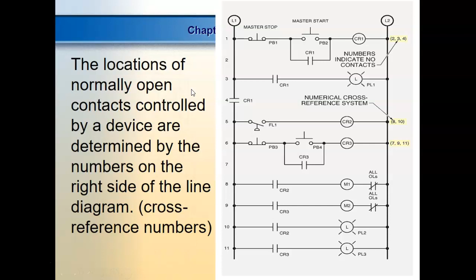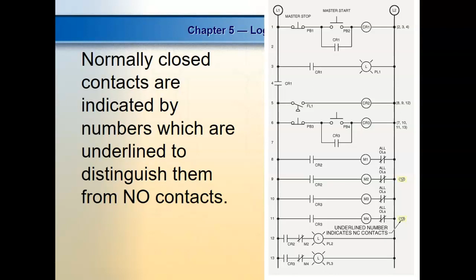All right, so normally closed contacts are indicated by numbers that are underlined. Whenever we use contacts that are normally closed, we underline them on the right. So our reference number tells us, hey, that's a normally closed contact that will open or disengage whenever the device it's connected to is energized. Okay? Does that make sense? Okay.